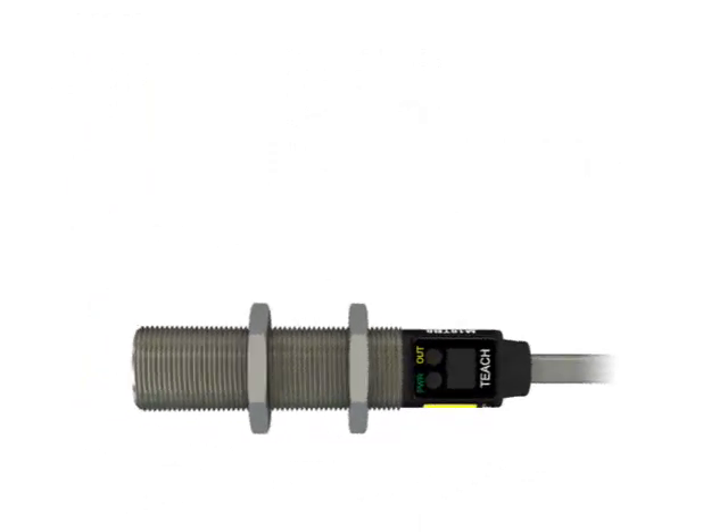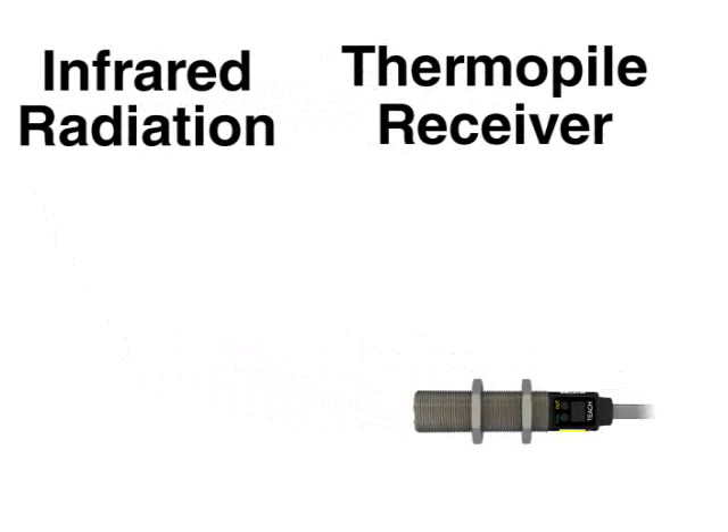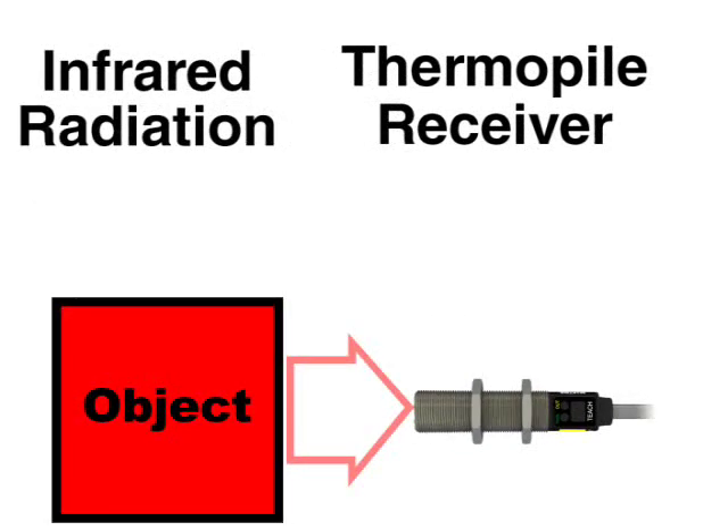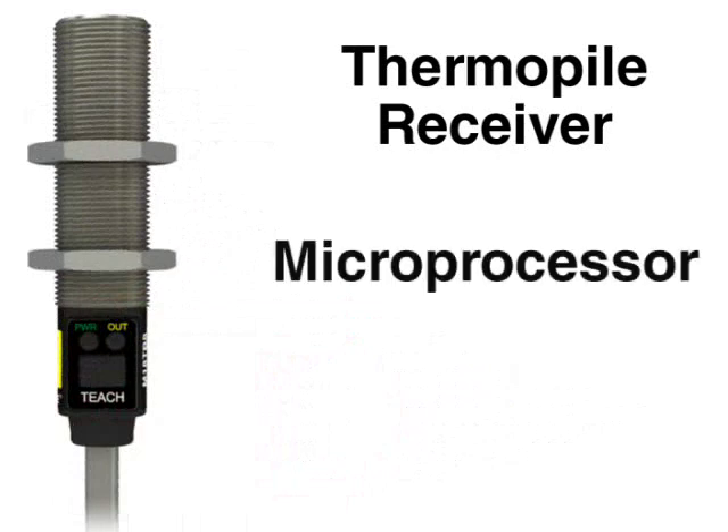To detect temperature, the sensor uses a thermopile receiver element to detect infrared radiation. As an object's temperature changes, its level of infrared radiation changes correspondingly. The thermopile is coupled to Banner's ASIC microprocessor technology, which compares the target information to the user-defined set point and determines whether the thermal contrast is adequate to energize the output.